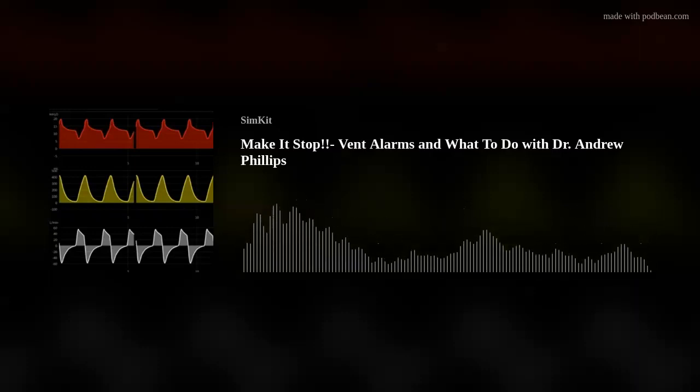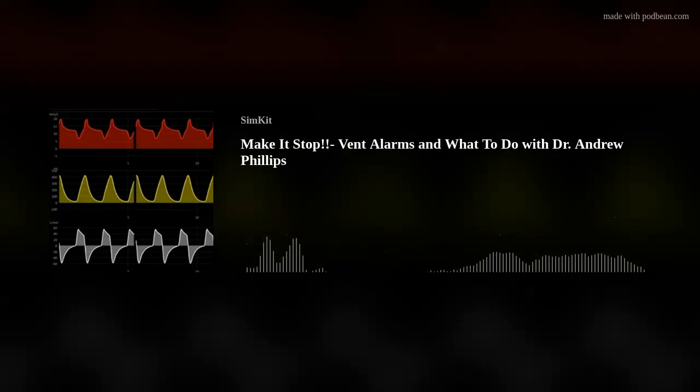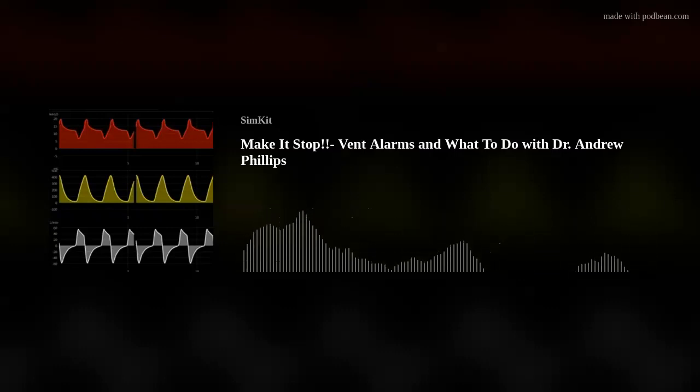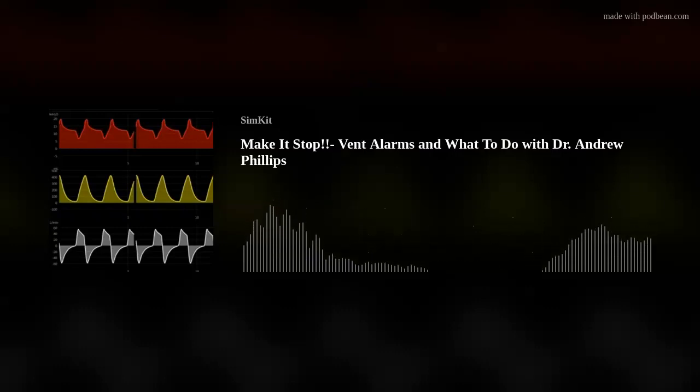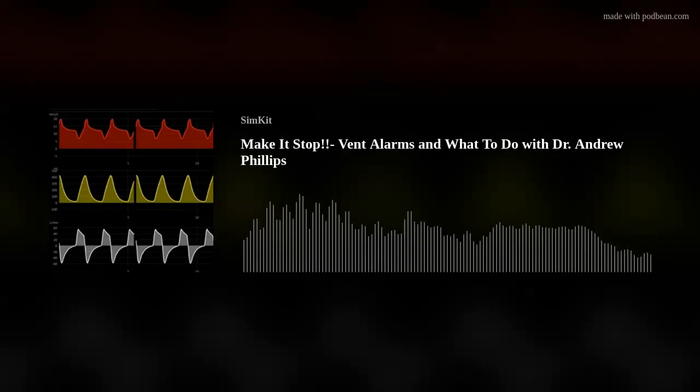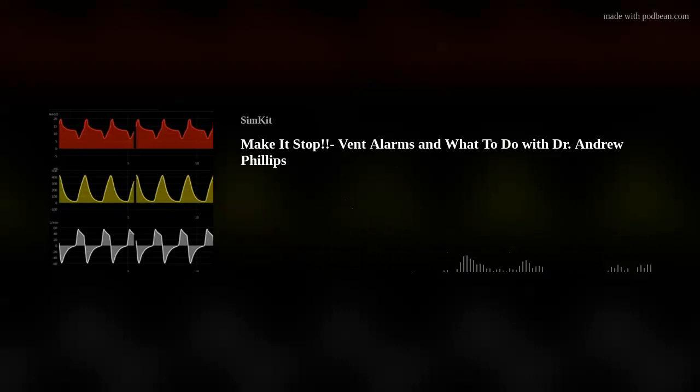There's an important difference between the peak pressure, and that's what's going to alarm, which is the highest pressure. It's a dynamic pressure. Anytime during the course of breathing, this alarm will go off if the pressure that's set is too high. And this could be any cause. It could be my fat foot stepping on the extension of the ET tubing going into the ventilator. That can cause a high peak. It can be any of that stuff.